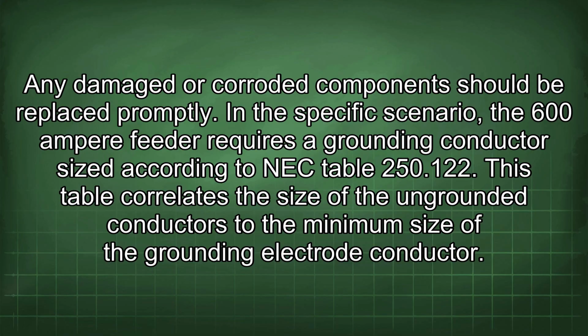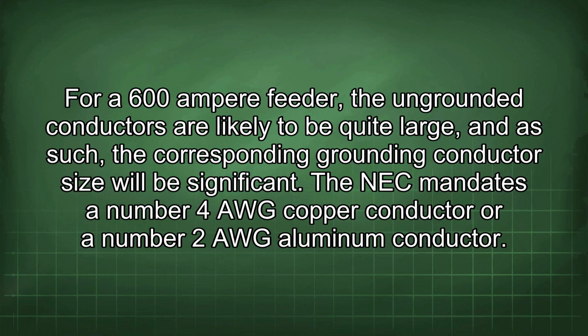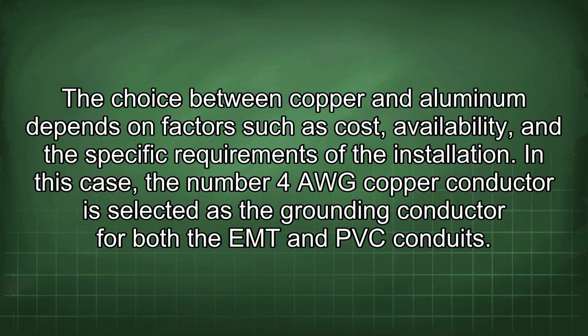In this specific scenario, the 600 Ampere feeder requires a grounding conductor sized according to NEC Table 250.122. This table correlates the size of the ungrounded conductors to the minimum size of the grounding electrode conductor. For a 600 Ampere feeder, the ungrounded conductors are likely to be quite large, and as such, the corresponding grounding conductor size will be significant. The NEC mandates a number 4 AWG copper conductor or a number 2 AWG aluminum conductor. The choice between copper and aluminum depends on factors such as cost, availability, and the specific requirements of the installation.